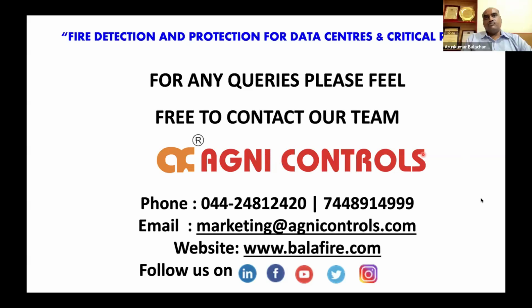Okay, so for a spot type detector, there is a height limitation the standard itself gives. We cannot go beyond 9 meters height for spot type detectors, and whenever it is coupled with a suppression system, we cannot go beyond 6 meters height. So for those applications, we can always go for an aspiration type smoke detector, also in combination with flame detectors as primary and secondary detectors.